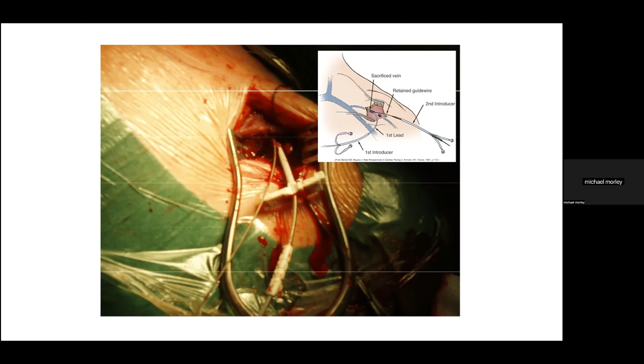Once we have got the lead in good position, we remove the stylet, and then we can apply some crocodile clips temporarily to the connections on the lead in order to test for sensing and for threshold, as we did with our temporary wire, to make sure that we've got a good signal, and to make sure that we've got an acceptable low threshold, which will maximize the battery longevity. If we are not happy, then we just move our lead and try and position it somewhere else.